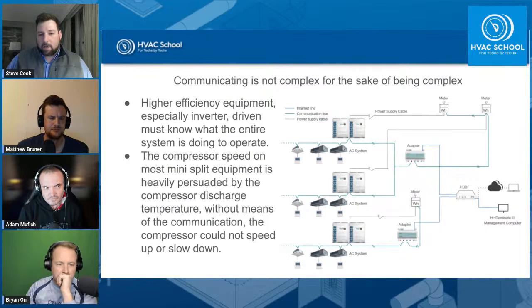Those voltages are what push the signal, but the communication itself is sent through data packets, pulses. So if an outdoor unit wants to know the temperature of an indoor unit, it'll send a pulse out saying, 'hey, I want to know your return temperature,' and that indoor unit will return a signal telling the outdoor unit what that return temperature is.